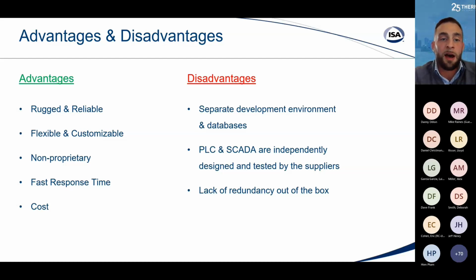Lastly, there's a lack of redundancy out of the box. Redundancy isn't there at all levels right away - it's available at the IO level, the controller level, the supervisory level, and the network, but it needs to be designed and implemented that way. It doesn't just come that way, and this adds to development and deployment cost.